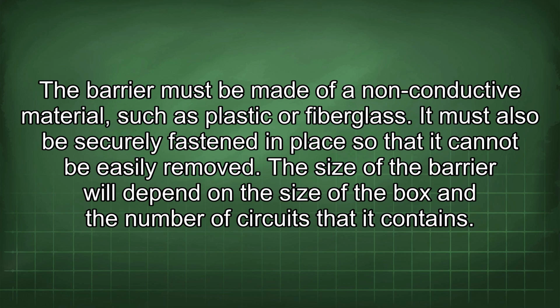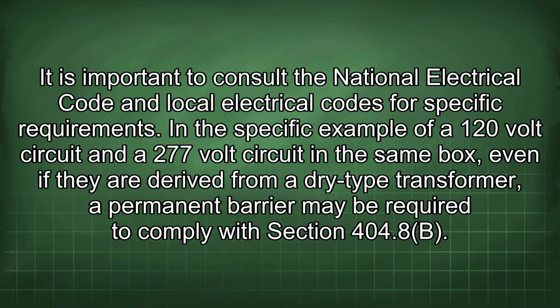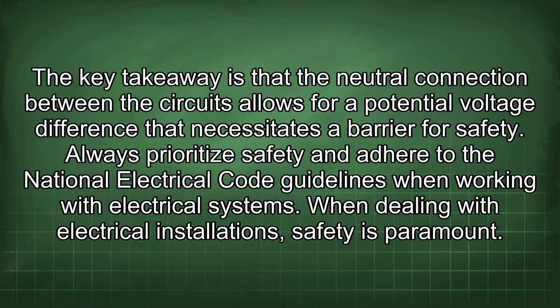The size of the barrier will depend on the size of the box and the number of circuits that it contains. It is important to consult the National Electrical Code and local electrical codes for specific requirements. In the specific example of a 120-volt circuit and a 277-volt circuit in the same box, even if they are derived from a dry-type transformer, a permanent barrier may be required to comply with section 404.8(B). The key takeaway is that the neutral connection between the circuits allows for a potential voltage difference that necessitates a barrier for safety. Always prioritize safety and adhere to the National Electrical Code guidelines when working with electrical systems.